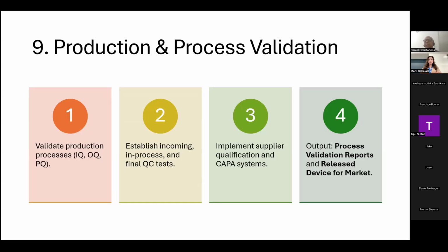The process parameters for lamination are time, temperature, and pressure. But such a simple process can become complicated because when you use adhesives, you may use adhesives from different companies, and each adhesive has certain characteristics. So you have to nail down a very good nominal for time, temperature, and pressure. This is where your engineering studies are very important, even before your so-called OQ—your real work is done during engineering studies.